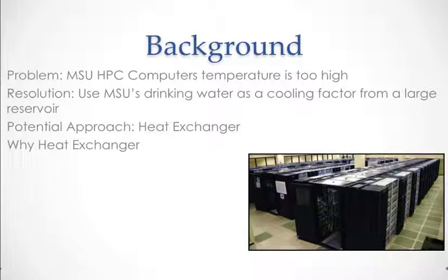The HPC is kept cool by a coolant. At Michigan State University, there is a large water reservoir located near the engineering building. In order to minimize cost, it was decided to use this water source in our heat exchanger to reduce the temperature of the coolant. Due to many environmental factors, the coolant needs to be harmless if ingested. Due to this, inhibited propylene glycol, otherwise known as Dowfrost, was used.